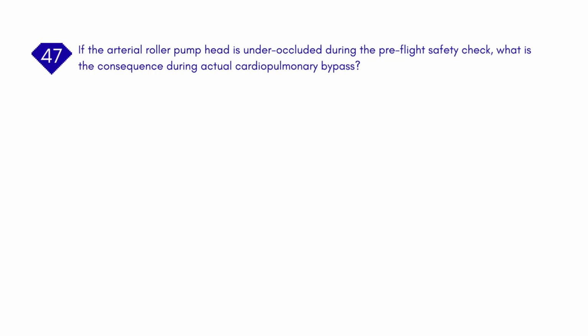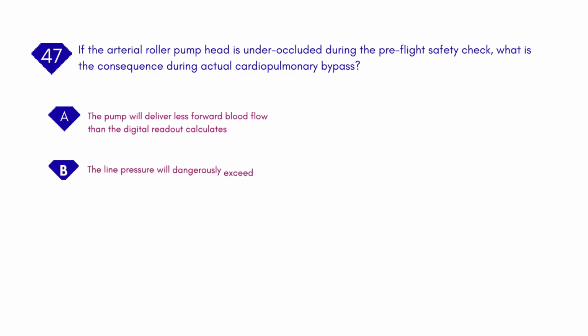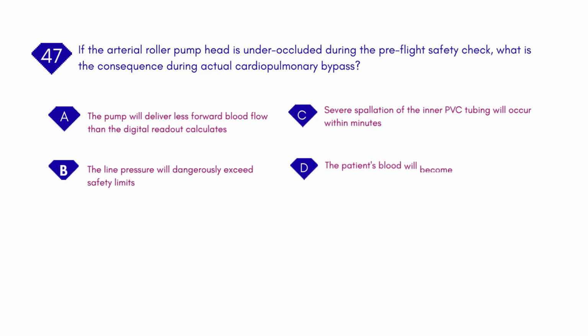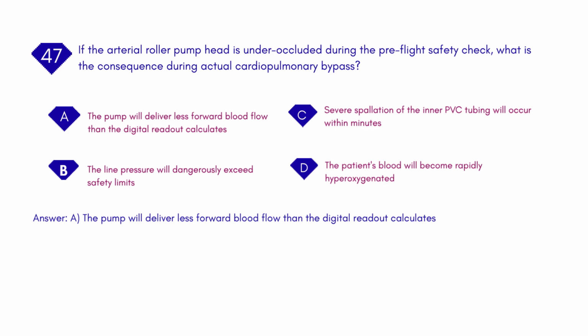If the arterial roller pump head is under-occluded during the pre-flight safety check, what is the consequence during actual cardiopulmonary bypass? A. The pump will deliver less forward blood flow than the digital readout calculates. B. The line pressure will dangerously exceed safety limits. C. Severe spallation of the inner PVC tubing will occur within minutes. D. The patient's blood will become rapidly hyperoxygenated. Answer: A. The pump will deliver less forward blood flow than the digital readout calculates.